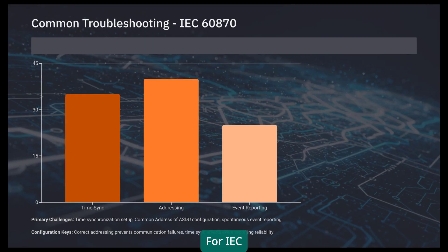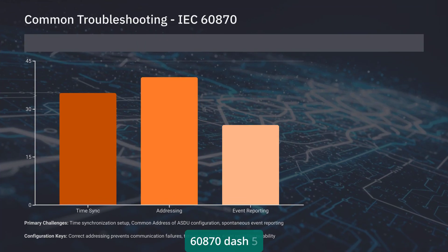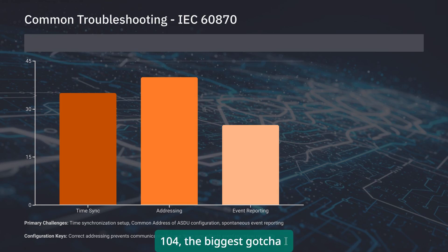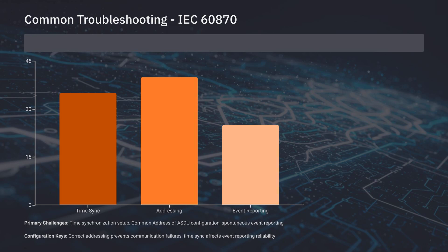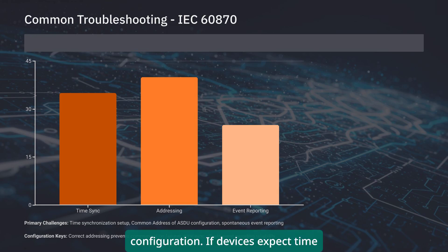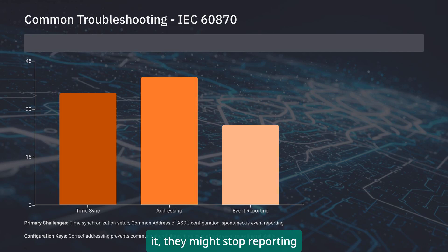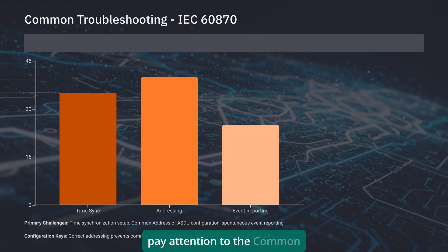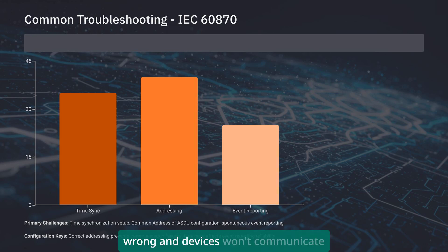For IEC 60870-5-104, the biggest gotcha is time synchronization configuration. If devices expect time sync but don't receive it, they might stop reporting spontaneous events. Also, pay attention to the common address of ASDU settings — get that wrong and devices won't communicate at all.